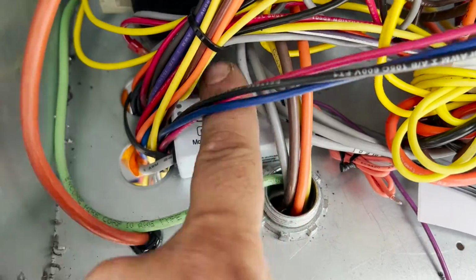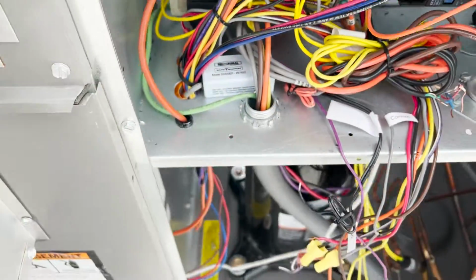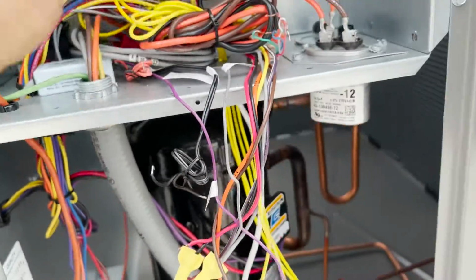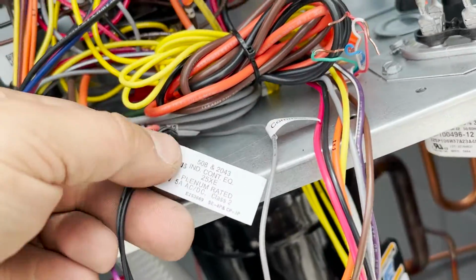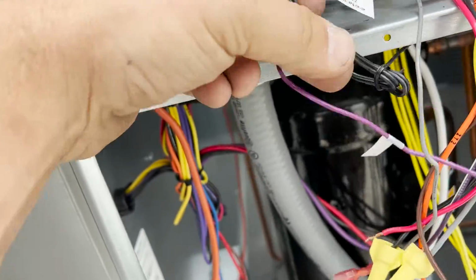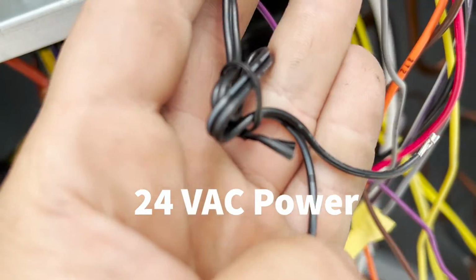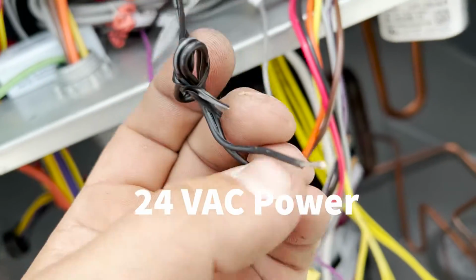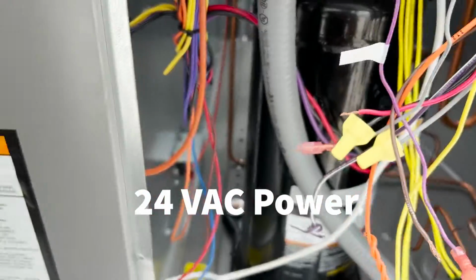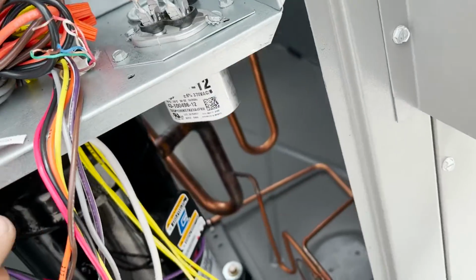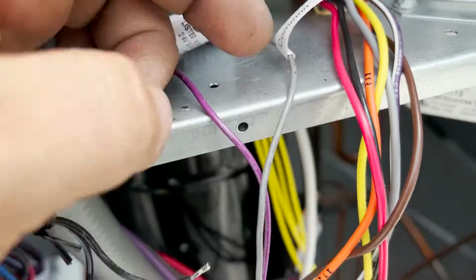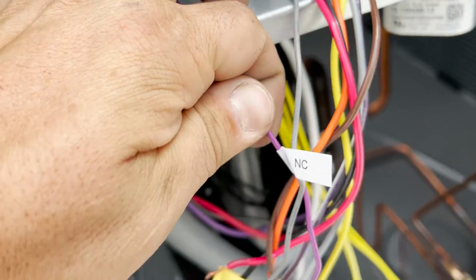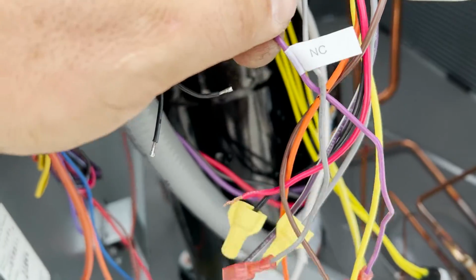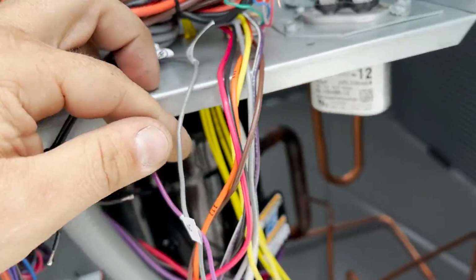All right, let's talk about this safety switch. So this is sitting in the pan. It's got 2 wires coming, well, 4 wires technically. This black set needs to go to power, right? White stripe is neutral, so common on white, red here. Anyway, that's not the big piece, right? So now we have common, okay, and normally closed, right? So unless this pan is flooded, this is just a connected piece.